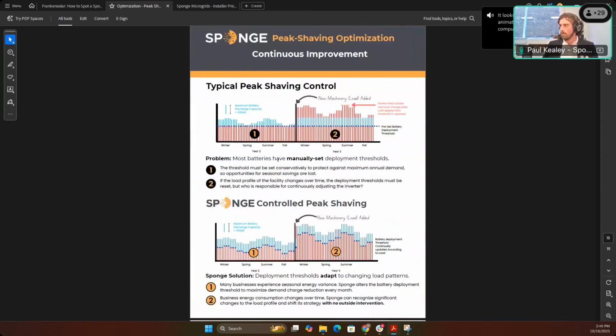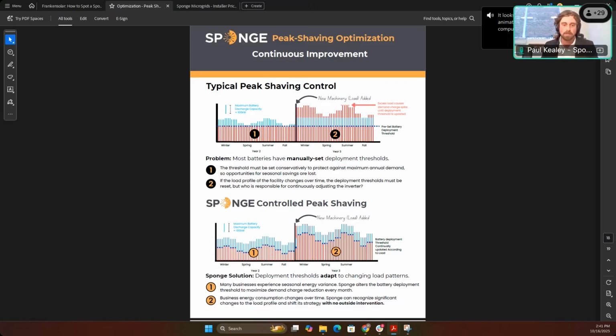And then there's some important considerations here with regards to how we differentiate ourselves in serving the peak shaving use case. So most batteries, as we've said, you just pre-program a preset battery deployment threshold. So you have a battery with maximum discharge capacity. You look at what the peak load on the year is, and your deployment threshold is effectively your peak load minus your battery capacity.